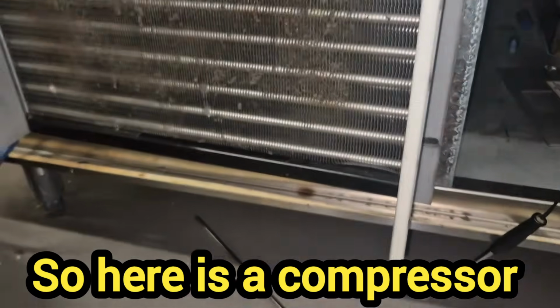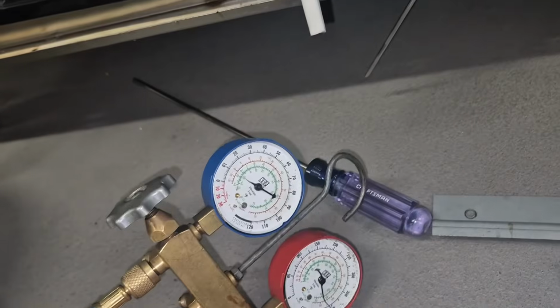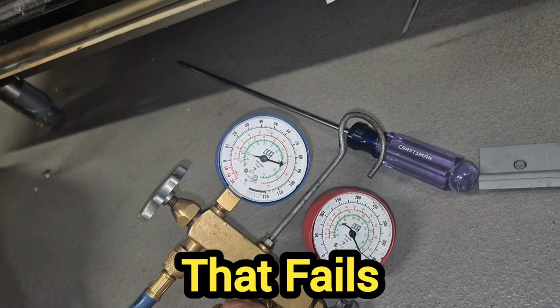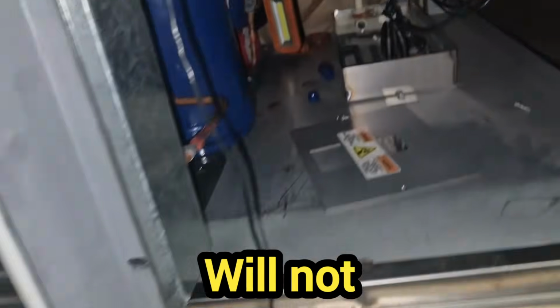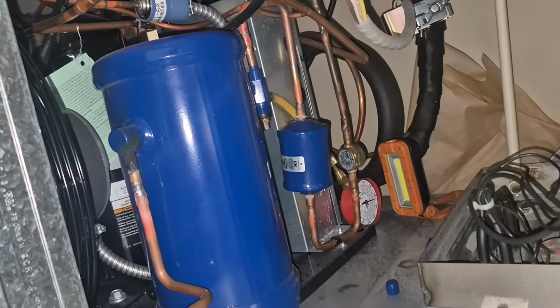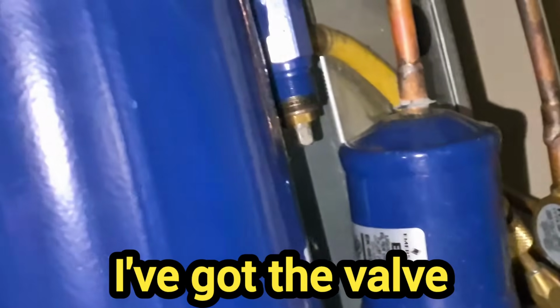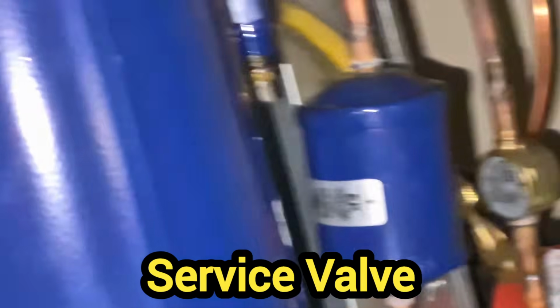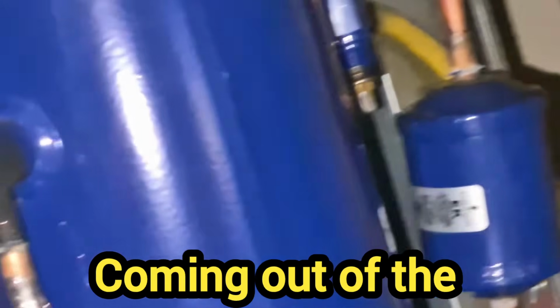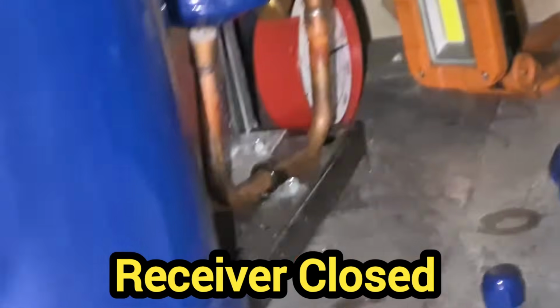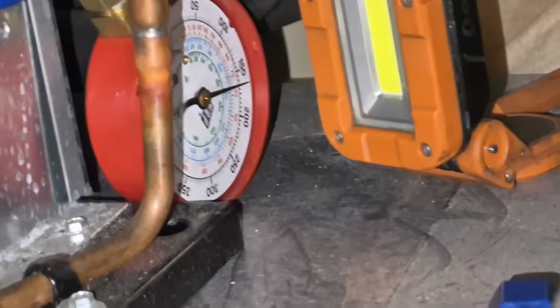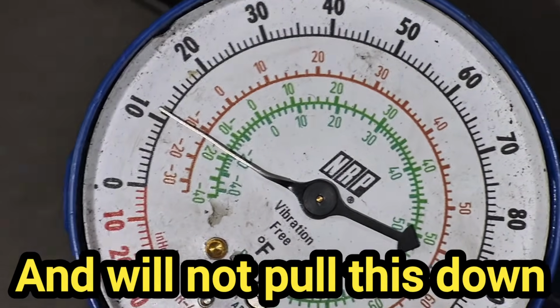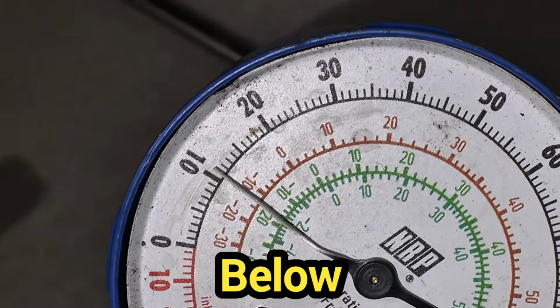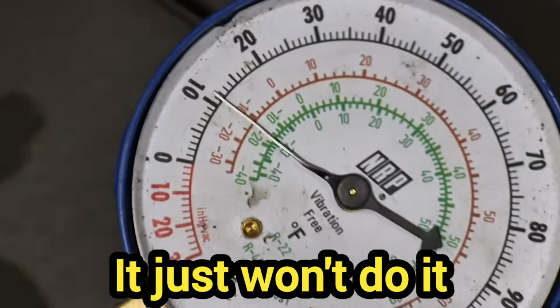So here is a compressor test that fails. This compressor will not pump down. I've got the service valve, coming out of the receiver, closed, and it will not pull this down below 11 PSI. It just won't do it.